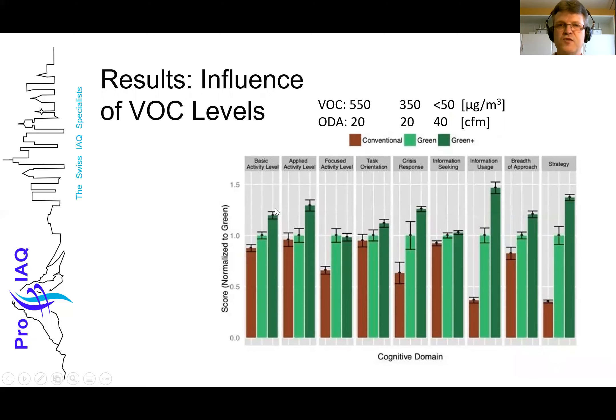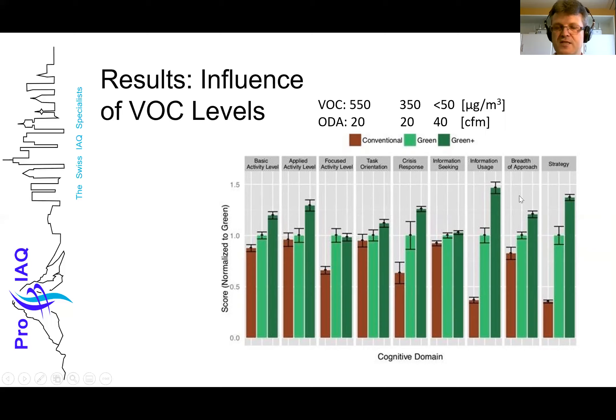Looking at the influence of VOC levels on cognitive output: we have a conventional building at 550 micrograms per cubic meter VOC, with the government-mandated limit being 2000. A green building is at 350, and a green-plus building is below 50. Looking at the function scores, basic activity level and especially information usage improve in the green-plus building — where the VOC is lower, the function score is better. Brain output gets much better if the air quality is better.